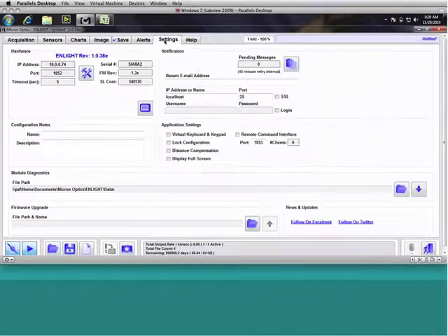In many cases, particularly when looking at relative strains in the absence of absolute temperatures, it is entirely acceptable and frequently convenient to ignore the effects of the speed of light offsets on the optical sensors and to simply establish a 0 point for a strain, zero that strain, and operate in a relative mode from there on out. So in many measurement situations, it's not necessary to set the distances.